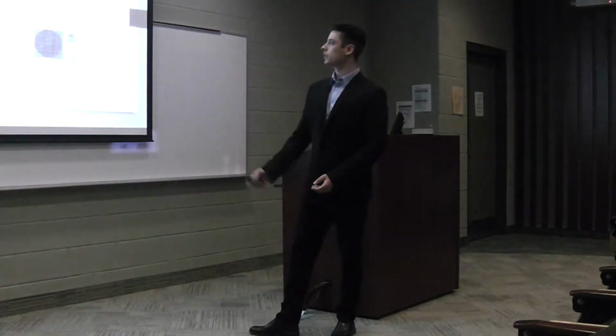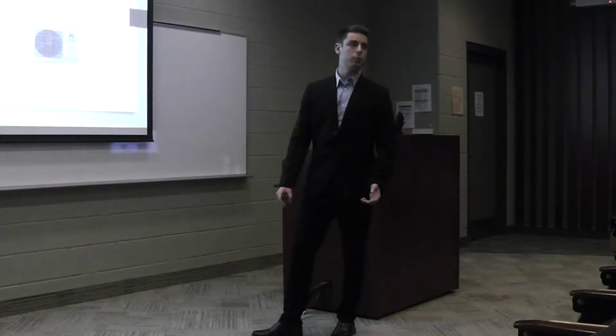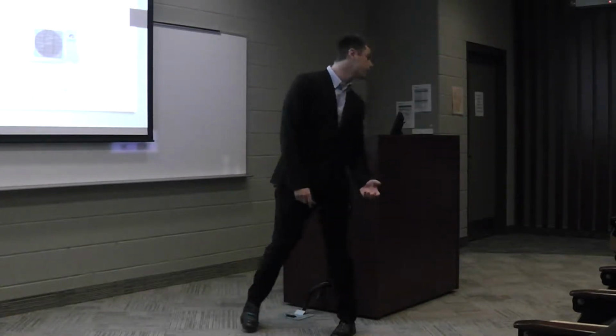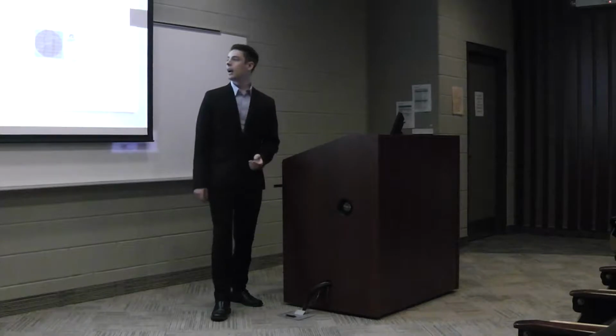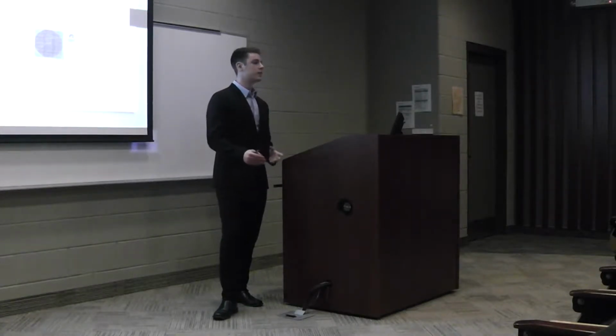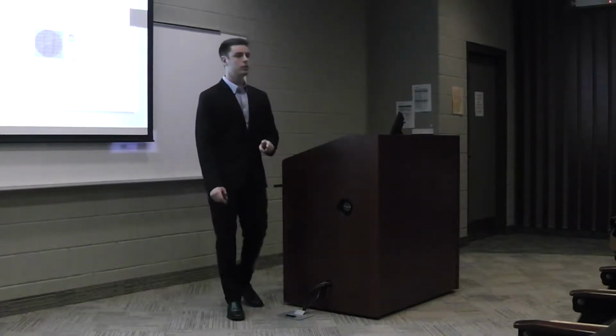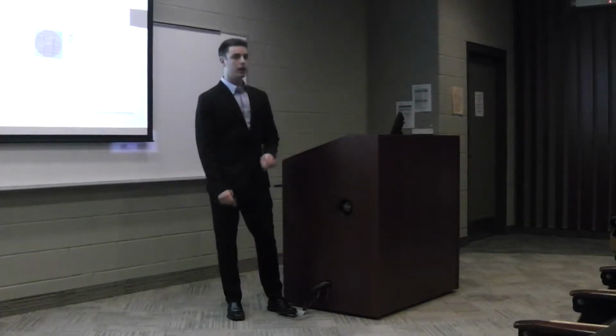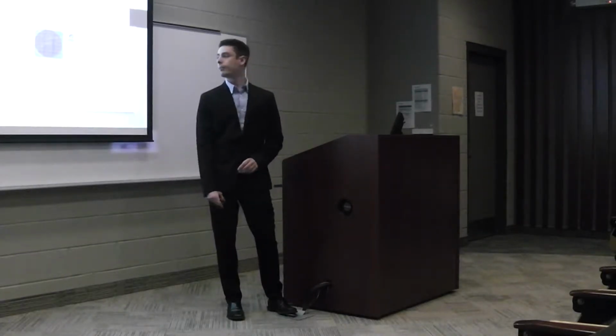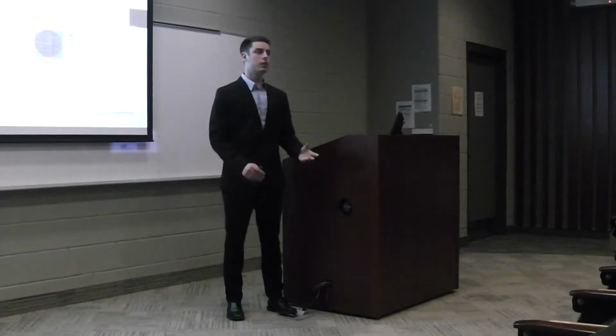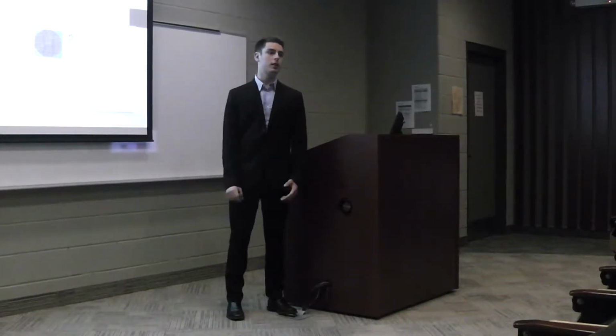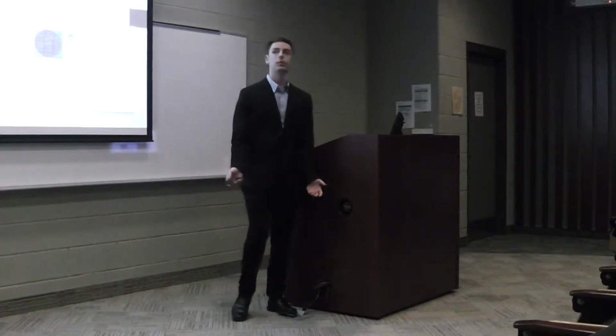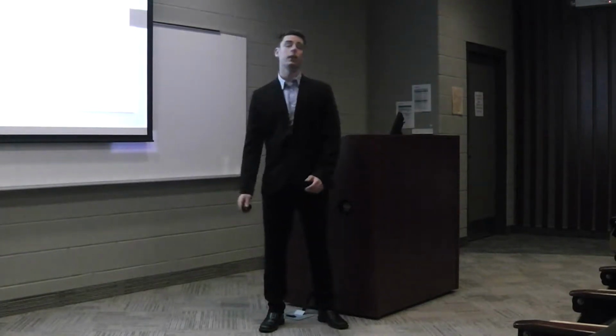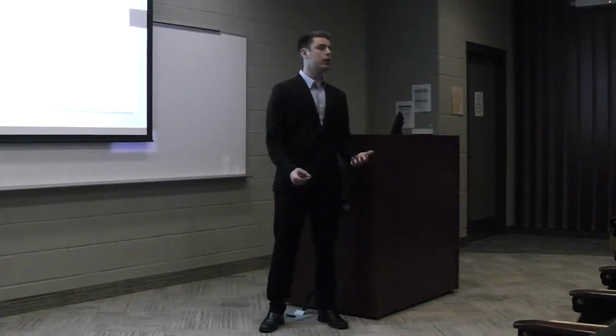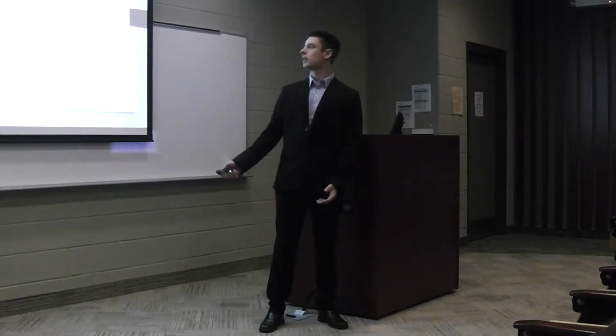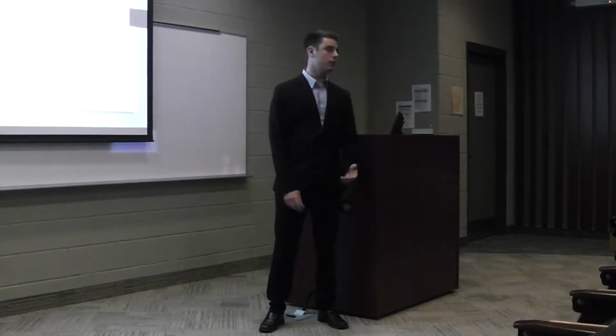So the two problems that I just mentioned: there's an abundance of heat put out through the summer because they do materials testing. And through the heating season, they have two systems in place, two ductless split heat pumps and an in-floor heating system. So we want to figure out if they can handle the heating load capacity, and if so, which one they should use. The heating load is a simpler calculation because of the conditions that the Gemtec laboratory is in.